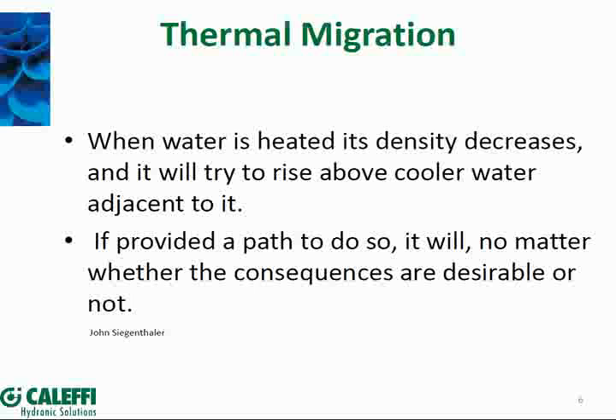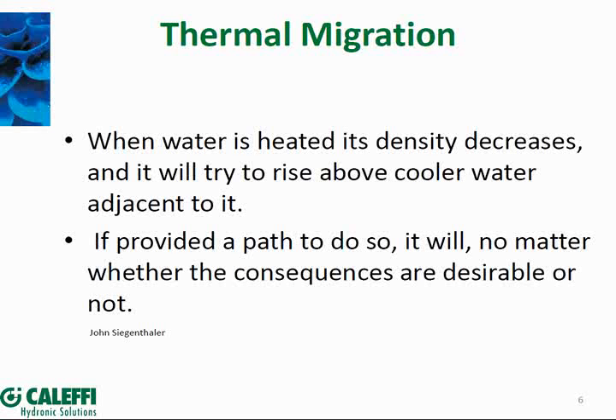We're going to talk about when thermal migration might be beneficial, when you don't want it, and different components or techniques you can use to eliminate or diagnose it. Basically, if there's a piping loop that provides a path for hot water to rise up and colder water to sink down, you get what's called thermal migration — sometimes called ghost flow.